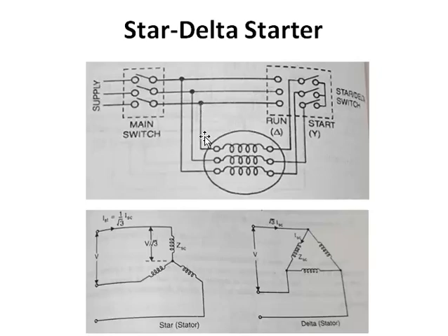See, this end is one end of the winding, and the other end will get connected with this point, and that point is the other end of one more winding. Similarly, this winding will get connected to the second winding, and the second end of the second winding will get connected to the first winding. This is how it makes the connection, so that is how it forms a delta connection.